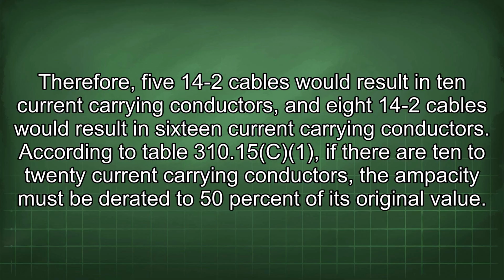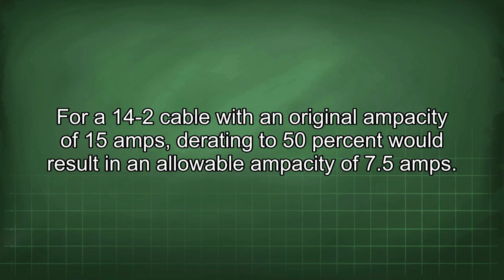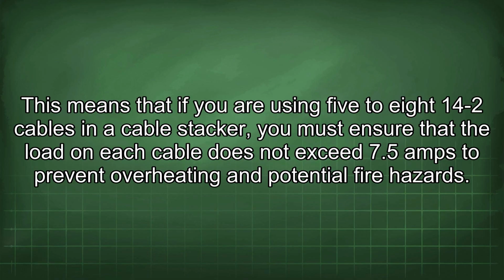According to Table 310.15, if there are 10 to 20 current-carrying conductors, the ampacity must be derated to 50% of its original value. For a 14-2 cable with an original ampacity of 15 amps, derating to 50% would result in an allowable ampacity of 7.5 amps. This means that if you are using 5 to 8 14-2 cables in a cable stacker, you must ensure that the load on each cable does not exceed 7.5 amps to prevent overheating and potential fire hazards.